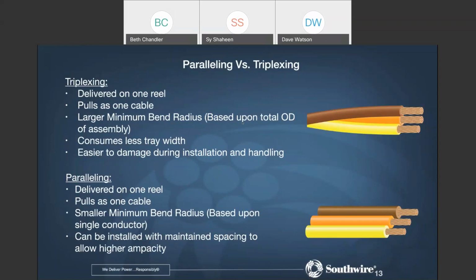Now, paralleling versus triplexing. On the paralleling product, you can see down at the bottom, delivered on one reel, it's going to pull as one cable. Now, the bending radius on this product is going to be based upon just the single conductor bend radius. So you actually end up with a smaller bend radius in total. And this can be installed with maintained spacing on cable tray installations.